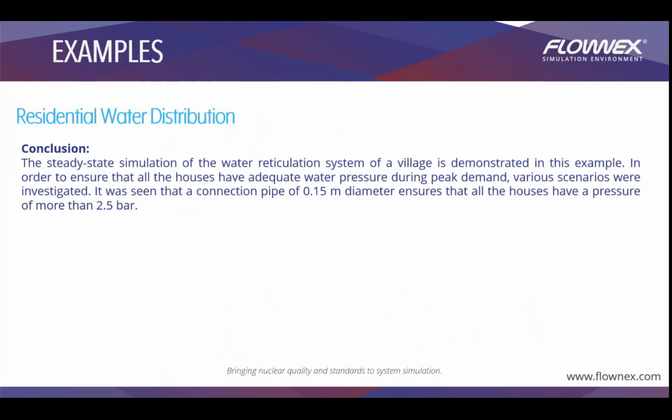The conclusion that we could draw from this was that the steady state simulation of the water reticulation system of a village was demonstrated in this example. As I mentioned, a new block was added to the settlement, and we had to maintain a certain pressure, and ensure that all houses have adequate water pressure during peak demand as well, so we had to maintain that 2.5 bar.